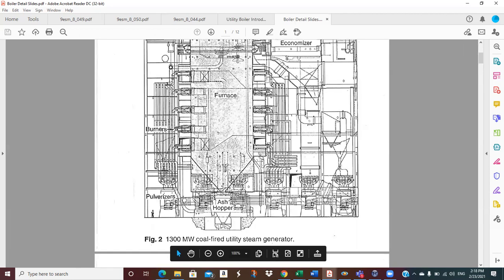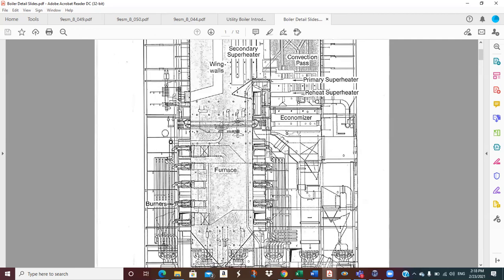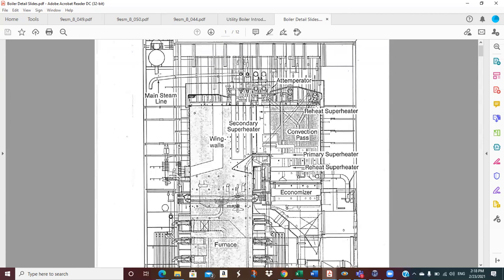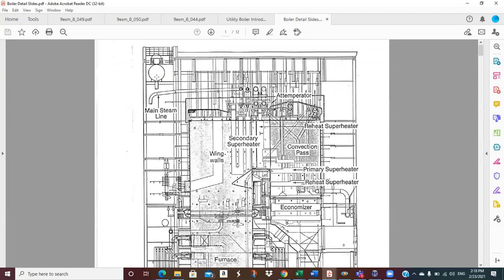And that water, it's being heated like crazy in here, so some of it's being converted to steam, and so it'll rise by natural convection and buoyancy effects back up to the drum where you separate the steam. The water just continues. You add water back to the drum. The steam goes out for superheating, and the water just continues to circulate through the boiler.